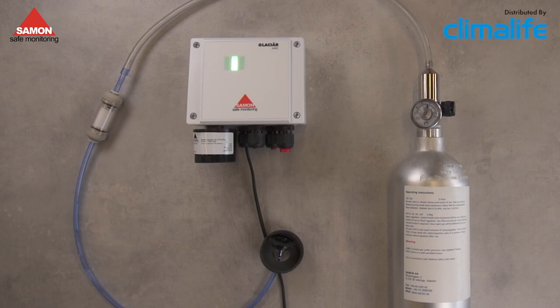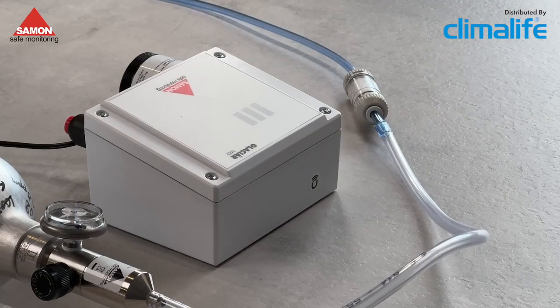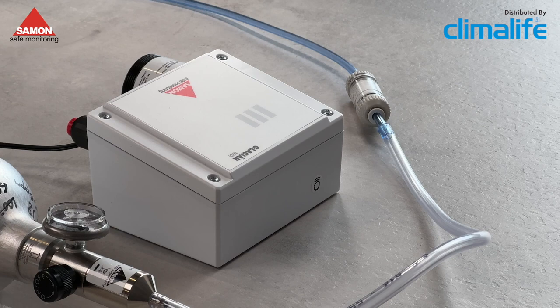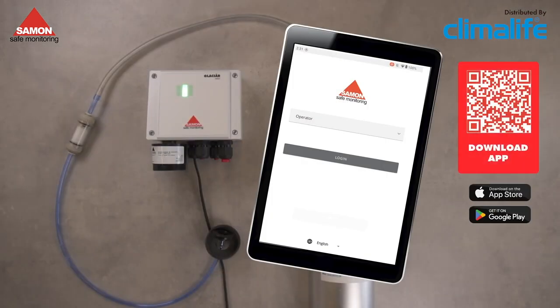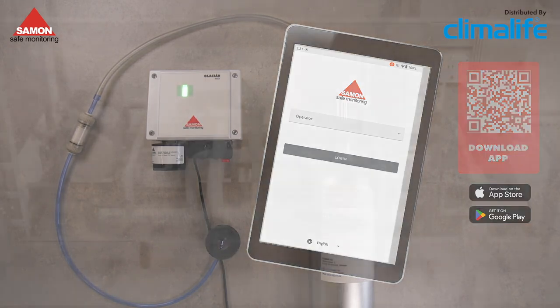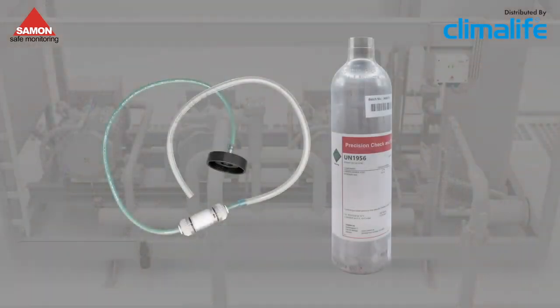In this step-by-step guide, we will show you how to calibrate the sensor on the Samon Glacier MIDI refrigerant gas detector. To calibrate the sensor, you will need the Samon Glacier Service app, which you can download for free for iOS and Android, a calibration kit and a test gas with a known concentration, typically between 50 to 100% of the measuring range of the sensor.